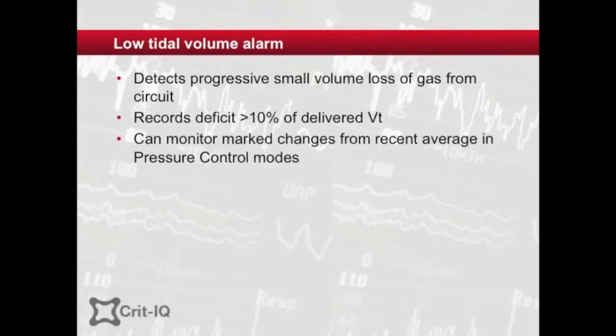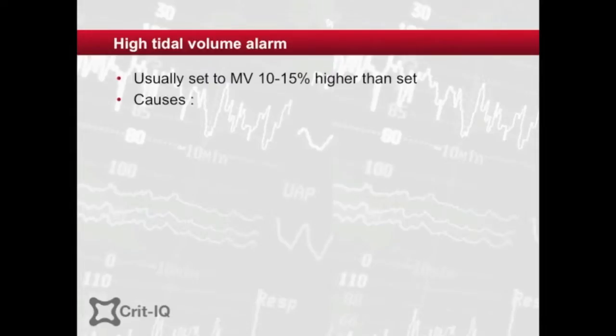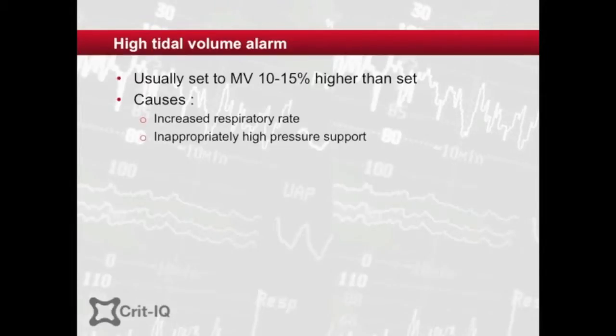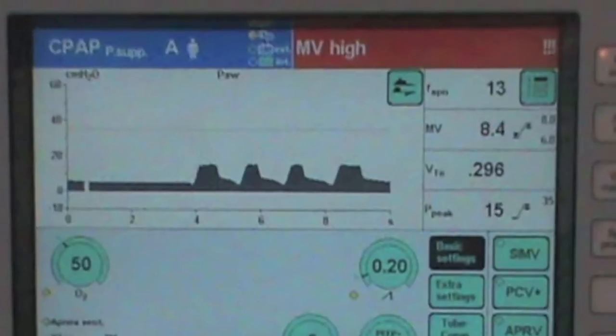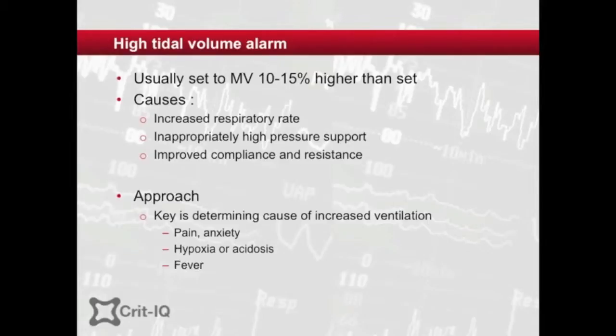In pressure-controlled modes, the tidal volume delivered is dependent on the pressure applied and the compliance and resistance of the system. Modern ventilators record average volumes and alarm when sudden deterioration of volumes occurs, suggesting a marked change in resistance-compliance characteristics. High tidal volume alarms may be triggered by an increased respiratory rate in assisted modes, pressure support settings that are too high for the patient, or changes in the patient's resistance and compliance in pressure-supported modes. The most important issue is to determine why the patient suddenly has a higher respiratory drive — usually related to pain, anxiety, hypoxia, acidosis, fever, or pulmonary embolism.